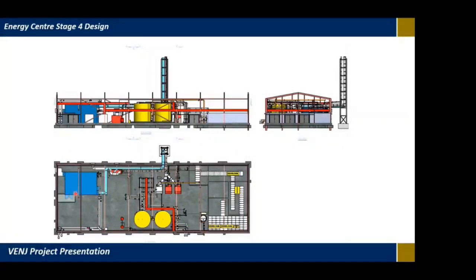Acoustically, the water source heat pump is quite loud. To save costs and avoid heavy acoustic treatment of the building itself, we asked the manufacturer to build an acoustic frame, a box around the heat pump. But due to the ammonia, all that had to be ventilated as well, so we needed background ventilation to keep it negatively pressurized in case of an ammonia leak.